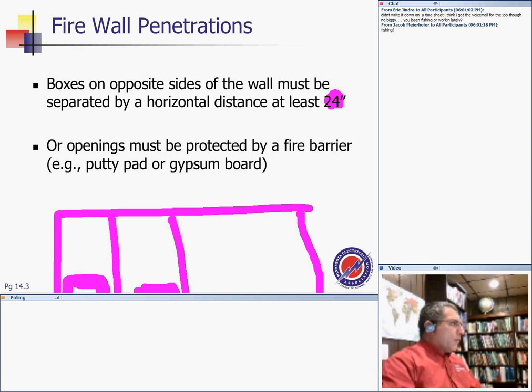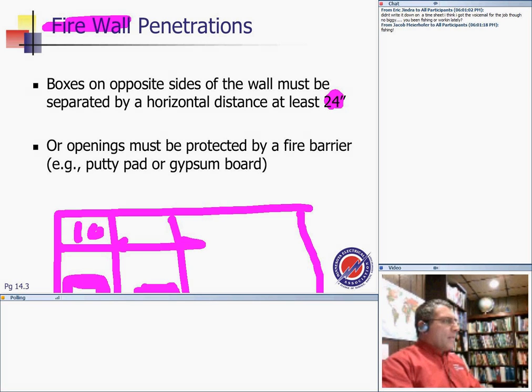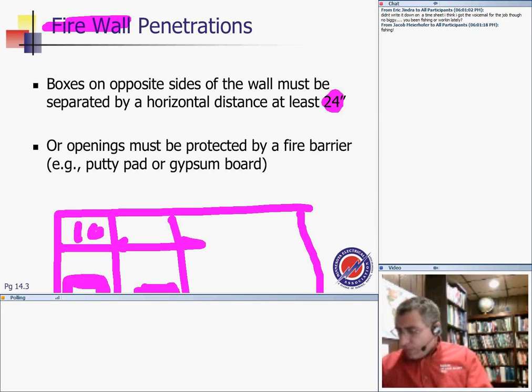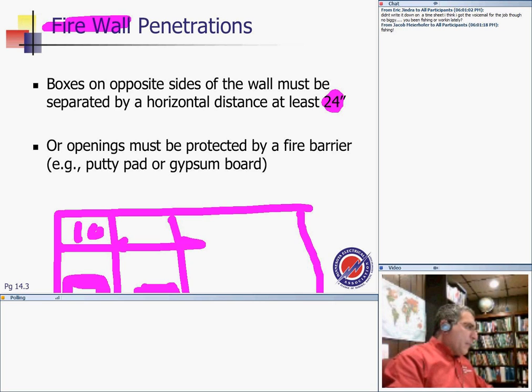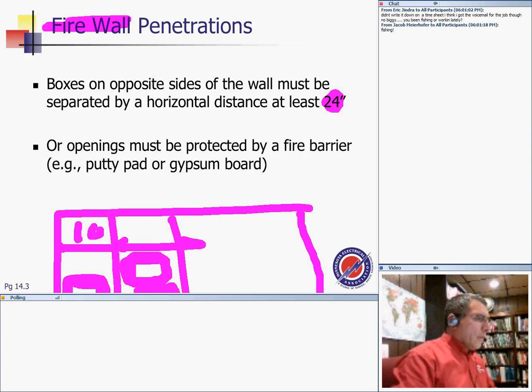The 24 inches, guys, in fire-rated walls, will guarantee they're not going to be in the same stud cavity, right? This is 16 inches, and 16 inches. So if they have to be 24 inches apart, they can't be in the same stud cavity. That's 24 to kind of guarantee that you don't put them in the same stud cavity. So if you have to put them back to back and so forth, then you have to protect them on both sides to maintain the integrity of the fire-rated wall.